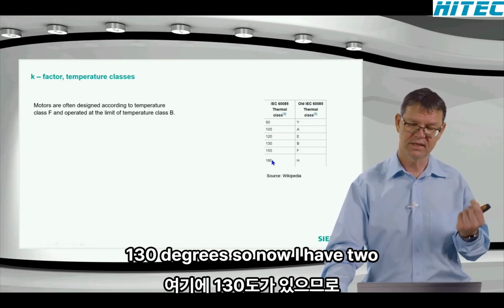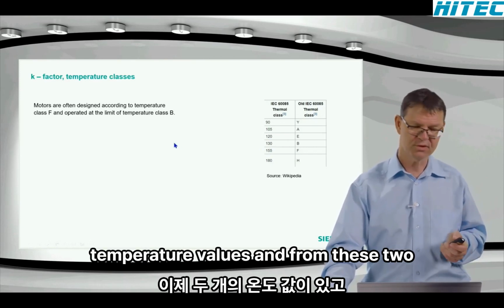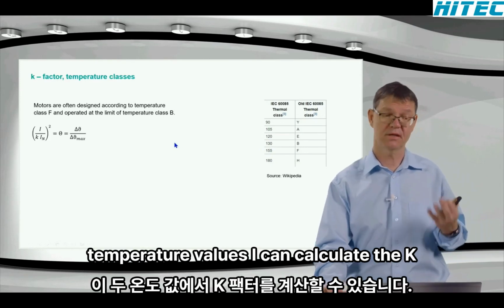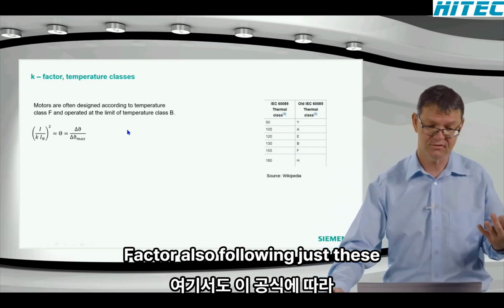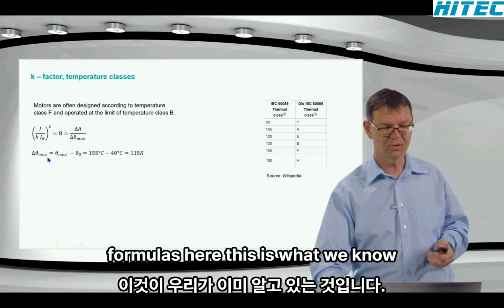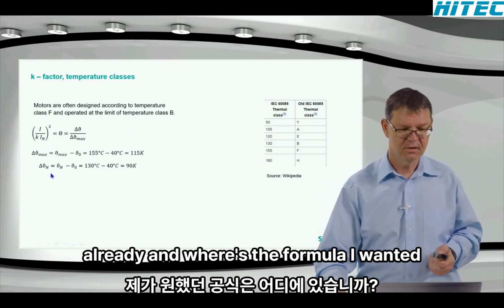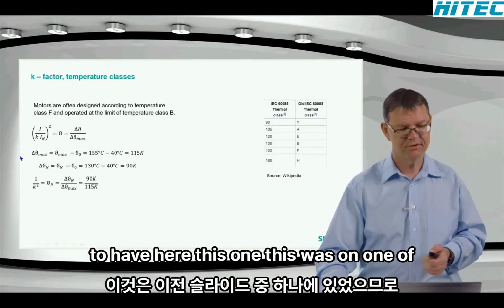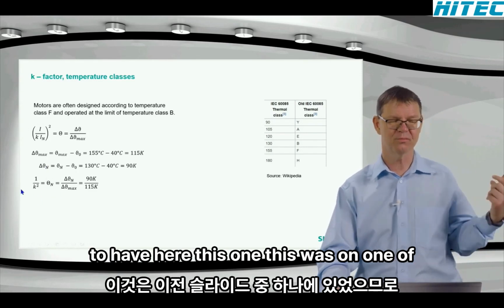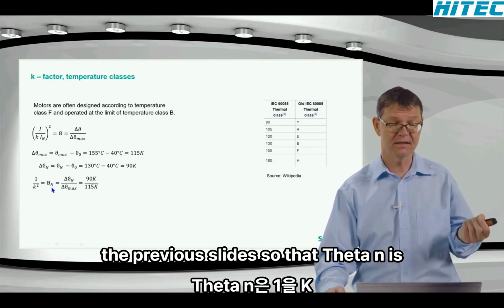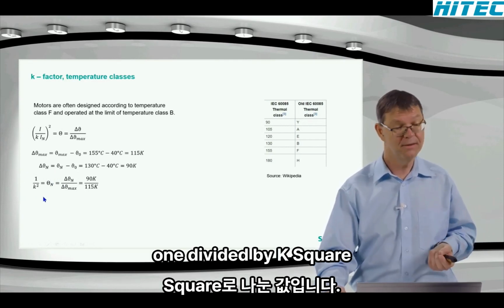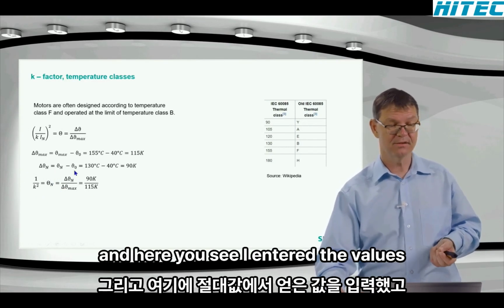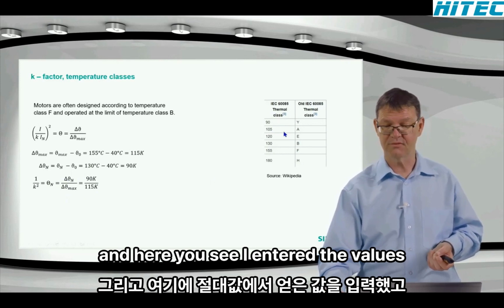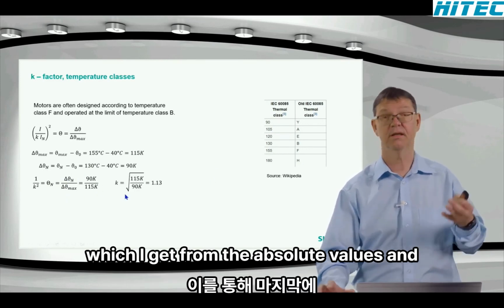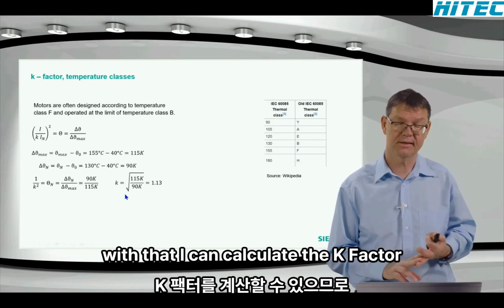So now I have two temperature values, and from these two temperature values, I can calculate a K factor also following just these formulas here. This is what we know already. And where's the formula I wanted to have here? This one, this was on one of the previous slides. So the theta n is 1 divided by K square. And here you see I enter the values which I get from the absolute values. And with that, I can calculate the K factor at the end.